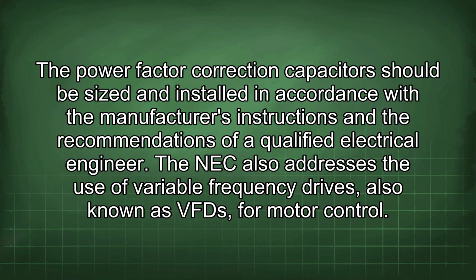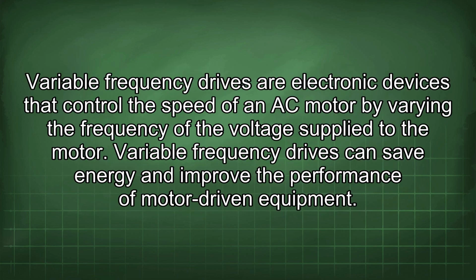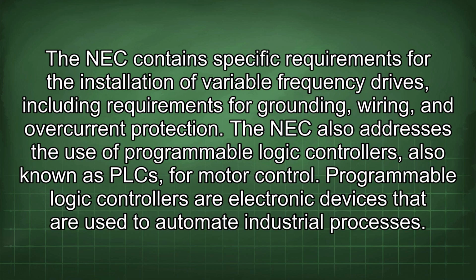a qualified electrical engineer. The NEC also addresses the use of variable frequency drives, also known as VFD, for motor control. Variable frequency drives are electronic devices that control the speed of an AC motor by varying the frequency of the voltage supplied to the motor. Variable frequency drives can save energy and improve the performance of motor-driven equipment. The NEC contains specific requirements for the installation of variable frequency drives, including requirements for grounding, wiring, and overcurrent protection.